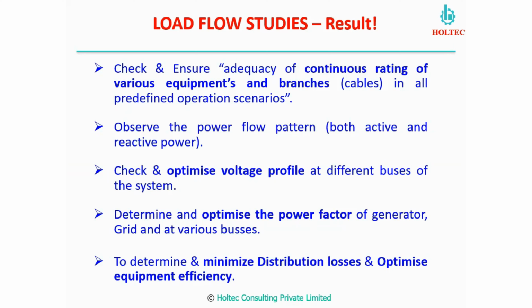If in generator, if we operate generators with lower power factor, what is happening? The copper losses, which is dependent on the I square of the current, will be increased, because with lower power factor, for same power output of the generator in terms of kilowatt, the current will be more. So when the current will be more, the load losses or copper losses which is happening in the generator itself will be high. So this is my personal observation, that normally people are not concentrating on the power factor improvement of the generator.